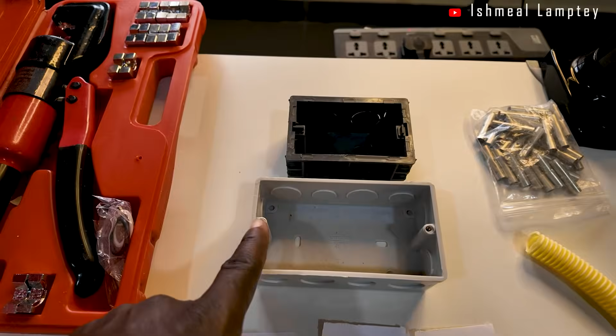Now, talking about 220 and 110, I've seen instances where one distribution board is used for both, which is not really right. If you have different systems, 110 and 220, it's important to have different distribution boards serving each of them. The reason is that when there are faults or problems, it's easier to trace, isolate, identify, and rectify them, as opposed to using one distribution board for both.